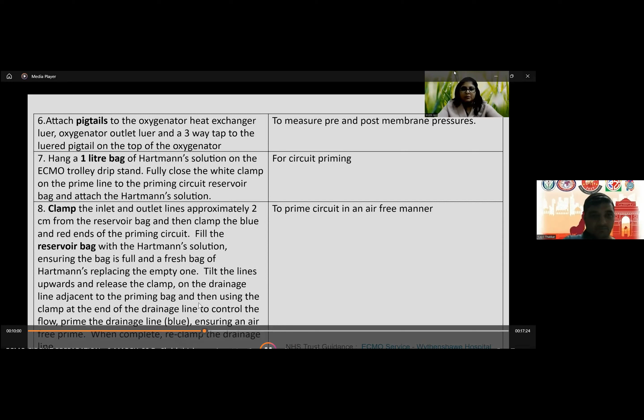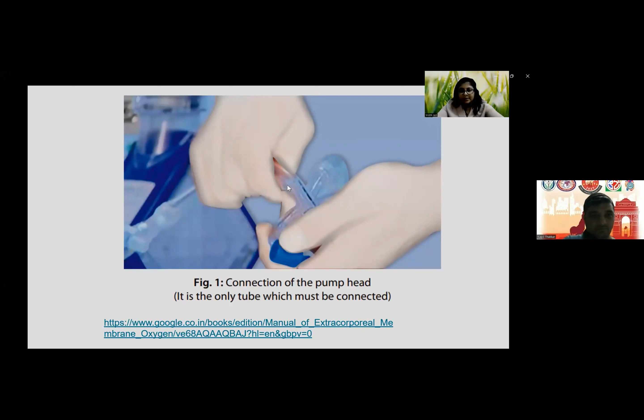So this is figure 1, and we can see that they are connecting the circuit to the pump head, and it is the only tube which must be connected, and it can sometimes be really hard to connect this tube, so we have to be really sure that it is connected properly, right? And once it is connected, you secure the tube to the pump head. Then you connect the tubes from the saline bags. This is how you connect the tube from the saline bags, and then you clamp the line between the 2 3-way cocks, right? So these are the 2 3-way cocks, and in between them you clamp the line.